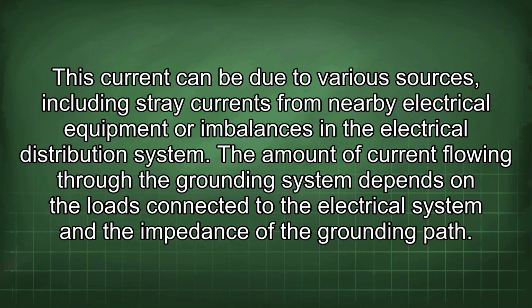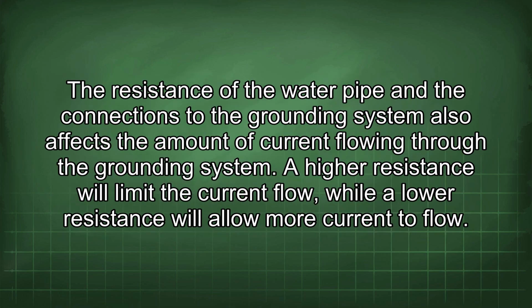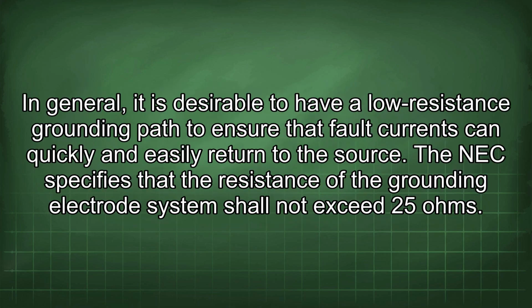This current can be due to various sources, including stray currents from nearby electrical equipment or imbalances in the electrical distribution system. The amount of current flowing through the grounding system depends on the loads connected to the electrical system and the impedance of the grounding path. The resistance of the water pipe and the connections to the grounding system also affects the amount of current flowing through the grounding system. A higher resistance will limit the current flow, while a lower resistance will allow more current to flow. In general, it is desirable to have a low resistance grounding path to ensure that fault currents can quickly and easily return to the source.